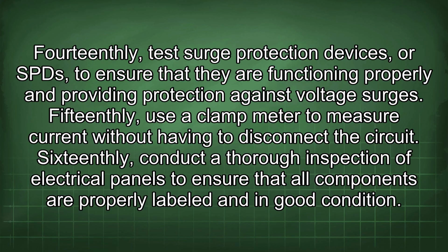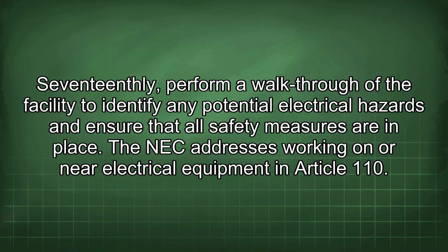15thly, use a clamp meter to measure current without having to disconnect the circuit. 16thly, conduct a thorough inspection of electrical panels to ensure that all components are properly labeled and in good condition. 17thly, perform a walkthrough of the facility to identify any potential electrical hazards and ensure that all safety measures are in place. The NEC addresses working on or near electrical equipment in Article 110.